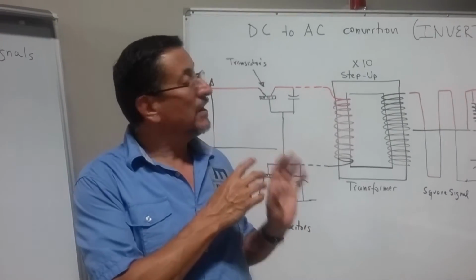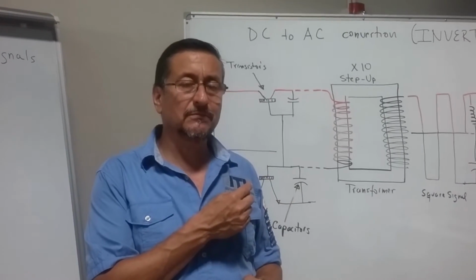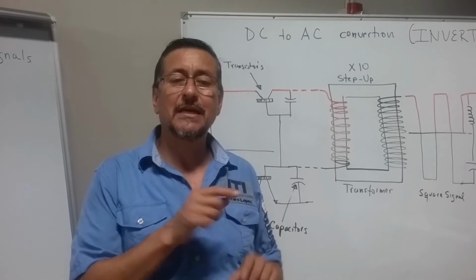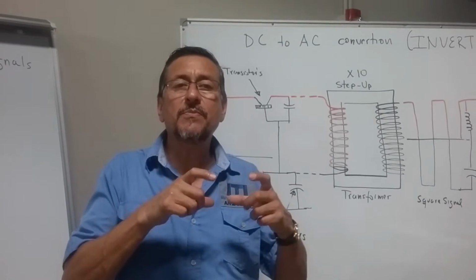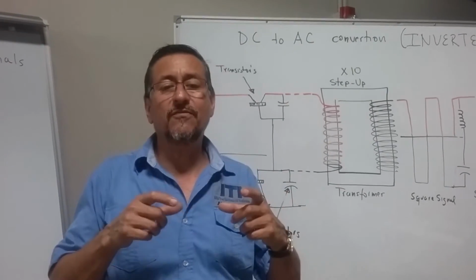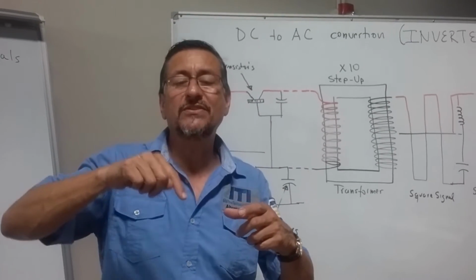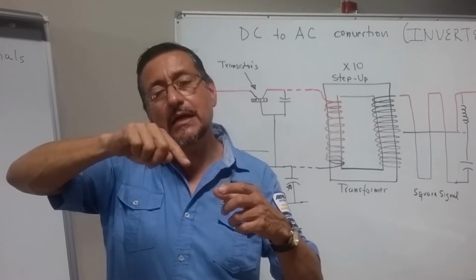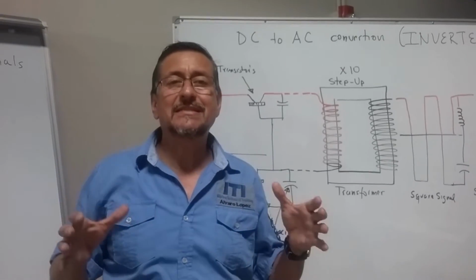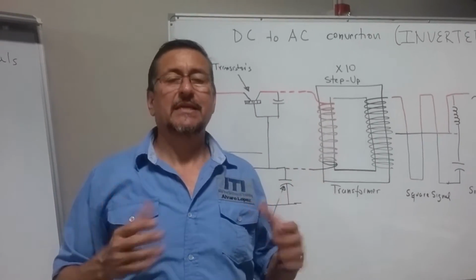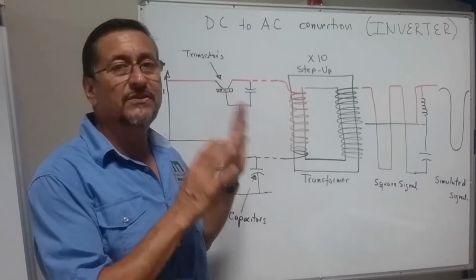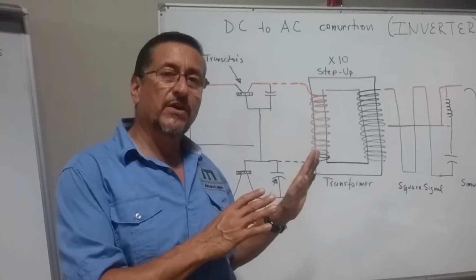In this particular case, we don't have electromagnets in rotation. We produce that signal in a circuit board. We interrupt the DC signal. We pass the signal through the step-up transformer, and we simulate that square signal. We round it, but that signal doesn't have frequency. This is the inconvenience of the signal produced on the inverter.